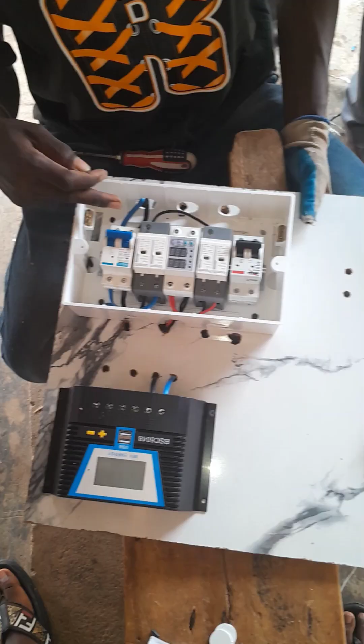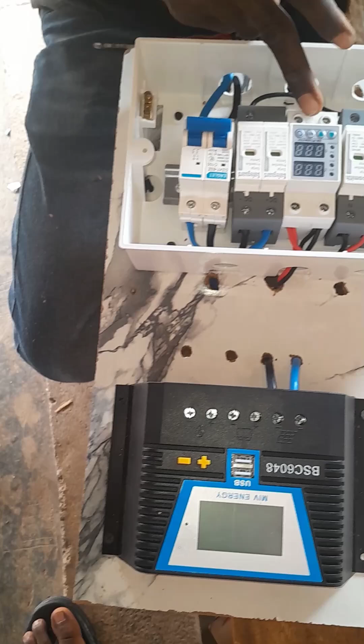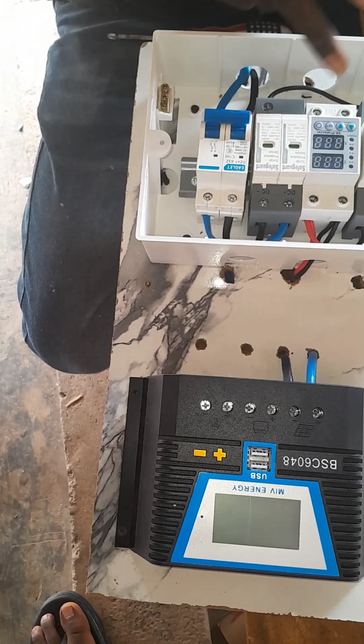DC breaker to our charge controller. Then from the panel it will enter from the top, which is the input, through the input of the surge. Then our output here from the DC surge is going to the earthing of the house. So this will be connected, while the work is in progress, to the output of our inverter.